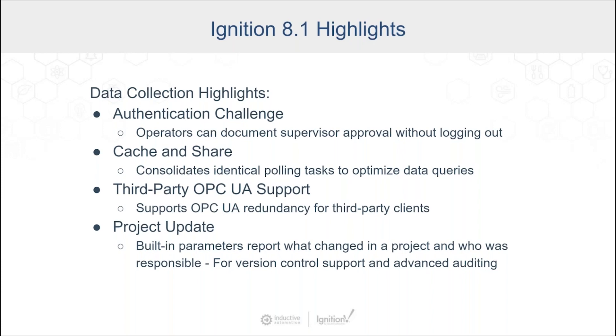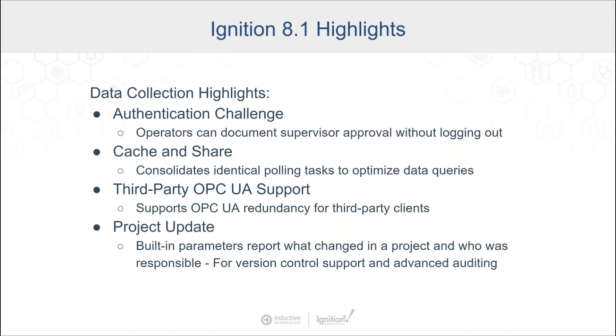Third-party OPC UA support: we added OPC UA redundancy which is nice if you're connecting to an external server that has support for that as it is inside the spec there. We added project update scripts that have better parameters to integrate with version control systems. If you're committing your changes to Git or another version control system so you can see the changes, it allows you to see who made those changes and log that information along with whatever commits you might be making.